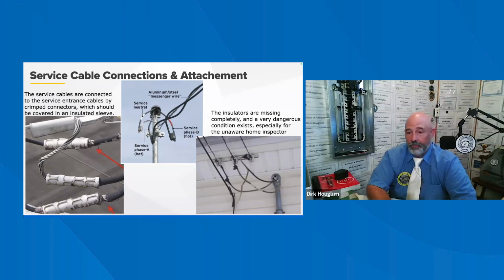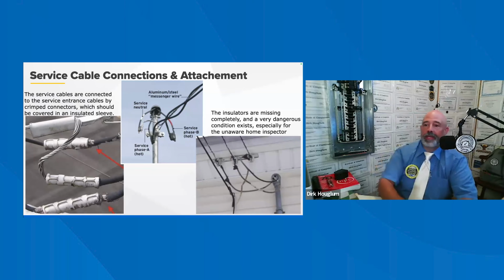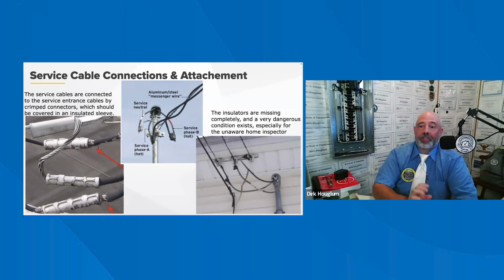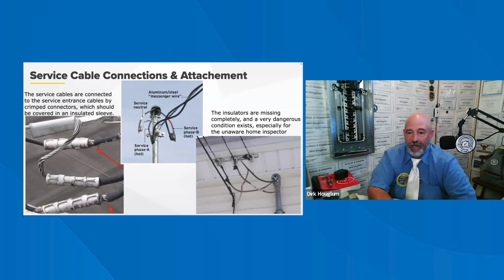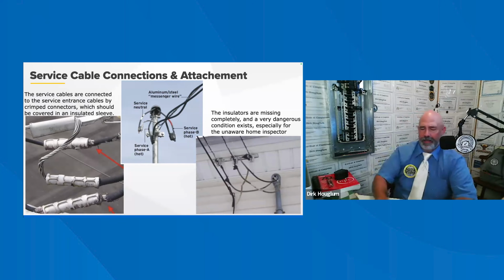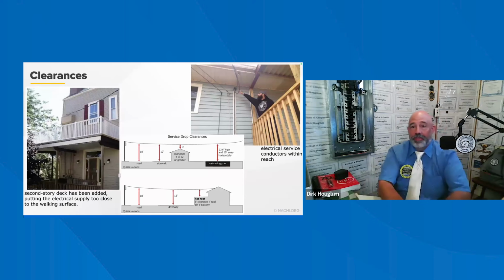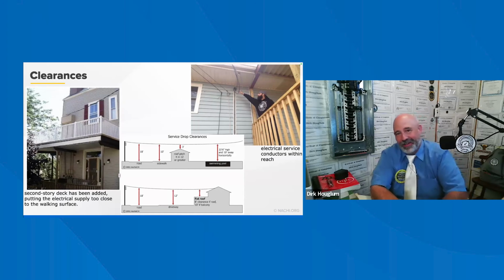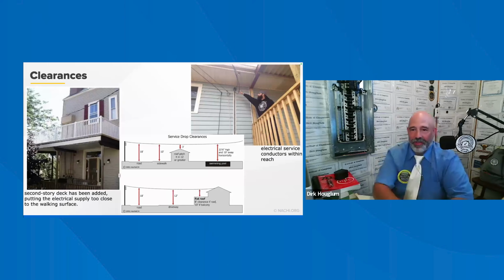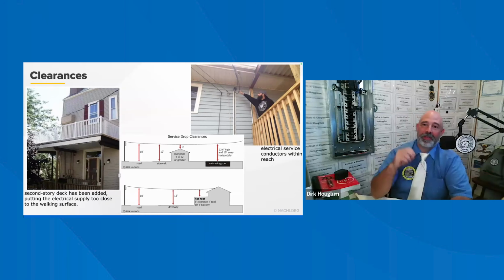We saw that in the slide a couple slides ago. On some older properties, the conductors are not in an accessible location, and each has its own connection to the structure. But this is rare these days and probably in need of replacement. The inspection image at the right shows one of those older ones. And I have seen those, but not very often anymore. The image on the left shows where a second story deck has been added, putting the electrical supplies too close to the walking surface. The overhead service must have a minimum separation from both the structure itself and any walkways, driveways, balconies, patios, and swimming pools. Very often an inspector will see properties that have been modified where the service overhead should have been relocated, but it wasn't.